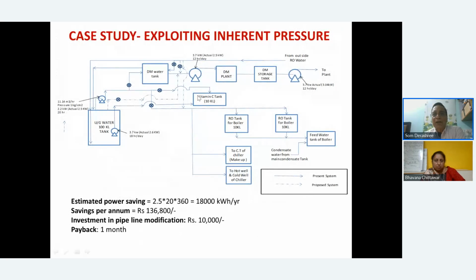Another example, exploiting the inherent pressure. There was somebody who was buying RO water from outside the company. This was being put into the underground tank, and then you had two pumps supplying to all this. Now this line itself had enough pressure. So what we did was we kept the system as it is, in idle, and just put this piping modification. This line is feeding all the systems directly with the inherent pressure in this line.